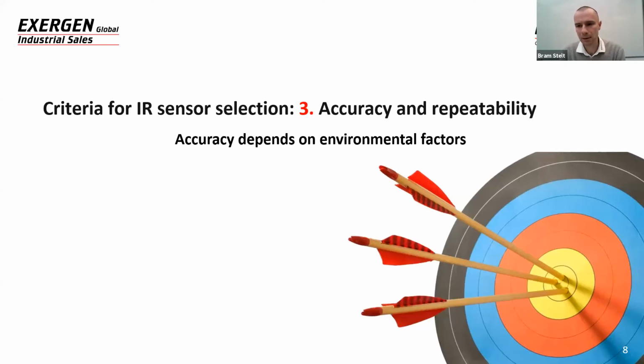The IRTCs in this way are really a high-end product, highly accurate and highly repeatable because of their unpowered nature. There's no power supply, there is no drift. So both on accuracy and repeatability, they score very high. And what you see is that in, for instance, medical applications, it's really important that there is a high level of accuracy because it concerns patient safety. So accuracy is really important.